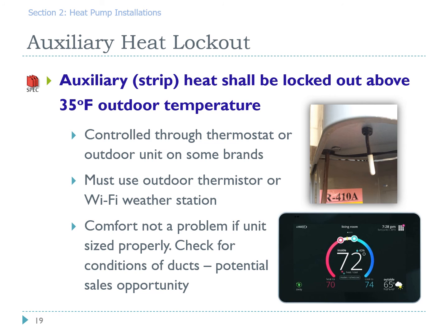One of the control specifications is auxiliary heat lockout. So we want to lock the strip heat out at any temperature above 35 degrees. This control setup is usually through a thermostat. Sometimes it's through an outdoor unit depending on the brand. And it uses a thermistor, which measures temperature, or it might use a Wi-Fi weather station if it's a Wi-Fi connected thermostat.